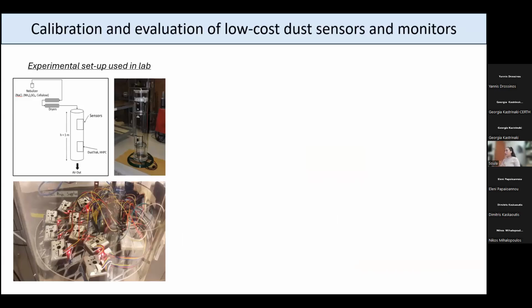So the first thing that I worked on for my master thesis was on the calibration and evaluation of low-cost dust sensors and monitors. This is the experimental setup that I used. I used a chamber which was approximately 1 meter tall, and it had a diameter of approximately 30 centimeters. At the top of the chamber, I had positioned the sensors, as you can see in the picture also. And at the bottom of the chamber, I had the reference instruments for the calibration and evaluation, which were the DustTrak and an HHPC.